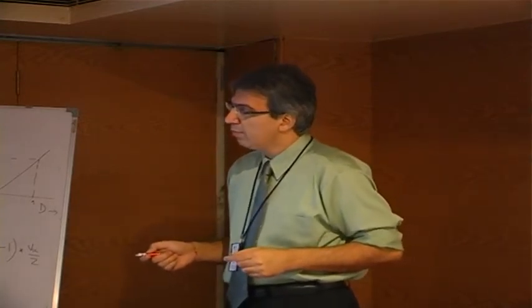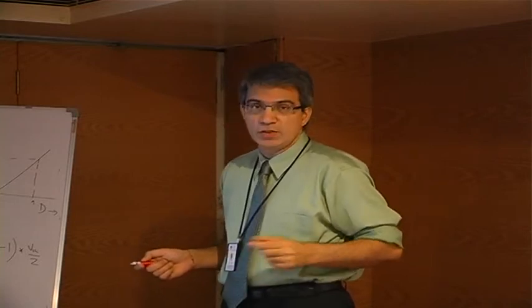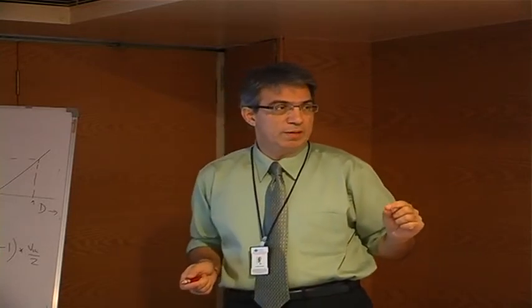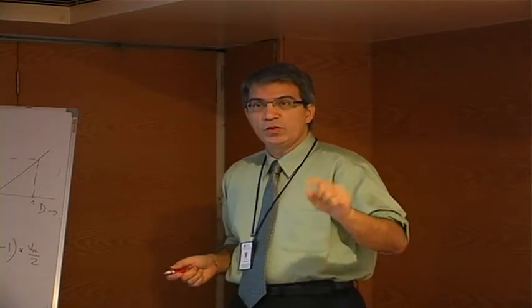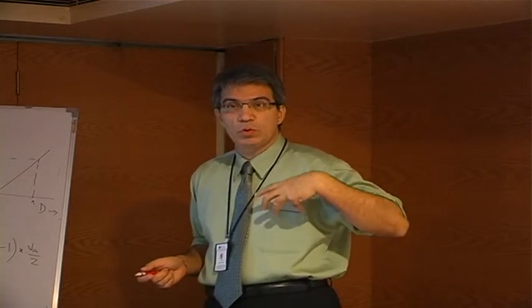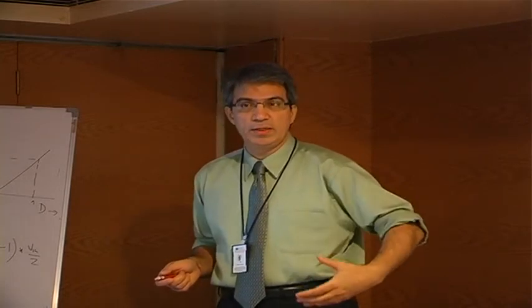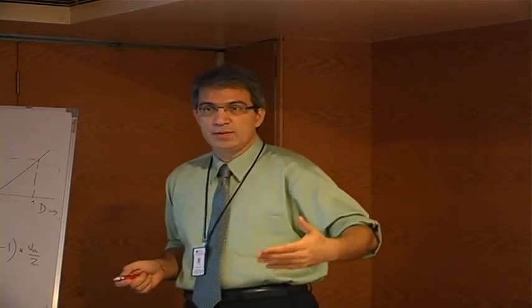And then you want to make sure MF must be an integer to eliminate sub harmonics at low frequency of rotation. This is very important. If your MF is not an integer, then you're going to see sub harmonics, and that will cause problems in terms of drawing a lot of current at slow speed because your inductance is not built up, so you can have a lot of circulating current in the motor.